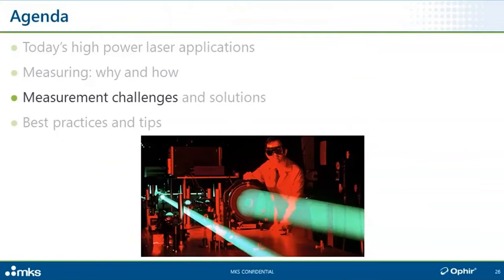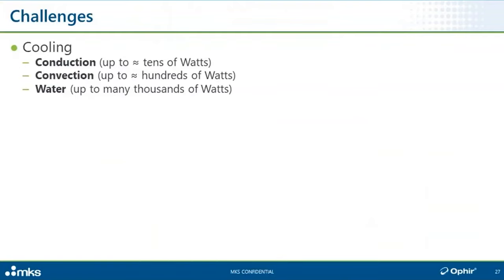We'll begin with the challenges. A high power laser beam carries a lot of, well, power. And when a sensor absorbs and measures that beam, the optical power of the beam turns into heat, which we need to remove from the sensor at least as fast as it's coming in. Otherwise, the sensor, as we said, is going to heat up, and eventually something is going to fail. Usually the first point of failure is going to be the thermopile junction, which would end up resulting in instant sensor death, as we might call it.